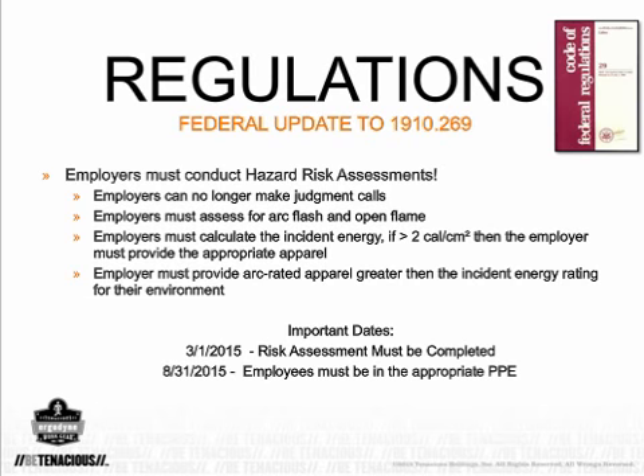For example, if an incident energy level is 8, then the apparel that would be worn must be 8 or greater. If your assessment shows you need a cal rating of 12, however, you cannot find an apparel item that meets that need, you may have to think about properly layering FR products together to be compliant. For an employer to be compliant, they must have the proper PPE from head to toe.